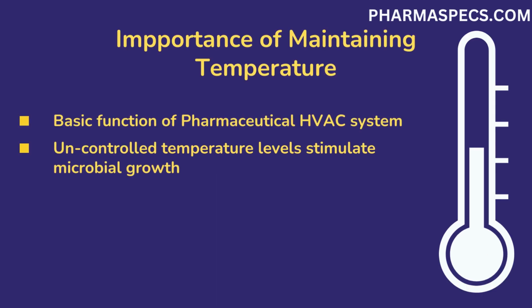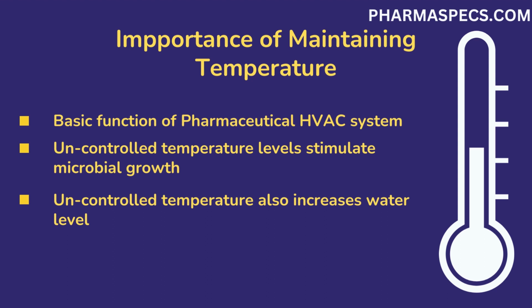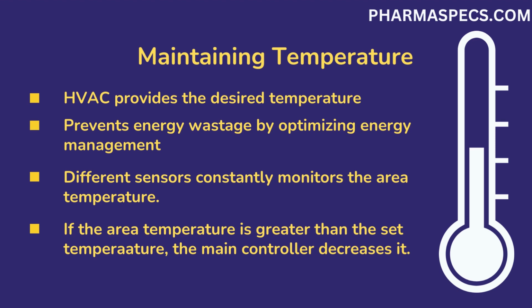Temperature control. Controlling temperature is an integral function of pharmaceutical HVAC system. Every pharma process is affected by irregular temperature values, and it also disturbs the cleanliness of the area because high temperature values are an ideal condition for microbial growth. High temperature also increases water level in the area, which also provides suitable conditions for microorganisms to grow. HVAC is used to provide the desired temperature levels. It also prevents energy wastage by optimizing temperature control of the area.